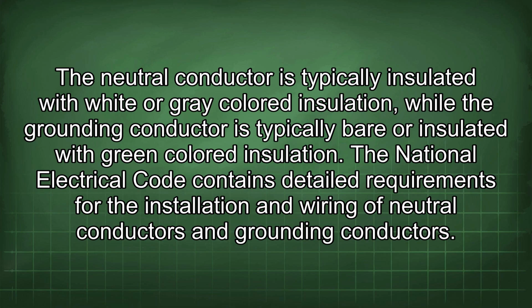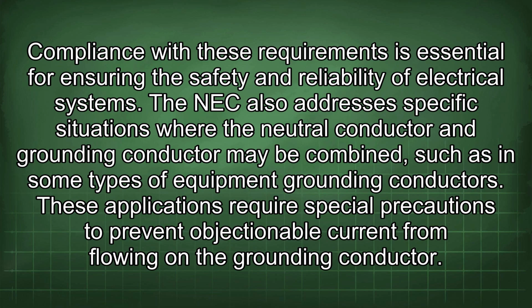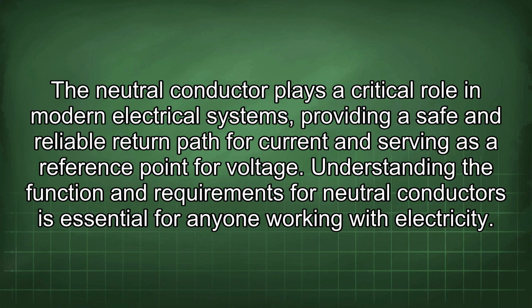The National Electrical Code contains detailed requirements for the installation and wiring of neutral conductors and grounding conductors. Compliance with these requirements is essential for ensuring the safety and reliability of electrical systems. The NEC also addresses specific situations where the neutral conductor and grounding conductor may be combined, such as in some types of equipment grounding conductors. These applications require special precautions to prevent objectionable current from flowing on the grounding conductor. The neutral conductor plays a critical role in modern electrical systems, providing a safe and reliable return path for current and serving as a reference point for voltage. Understanding the function and requirements for neutral conductors is essential for anyone working with electricity.